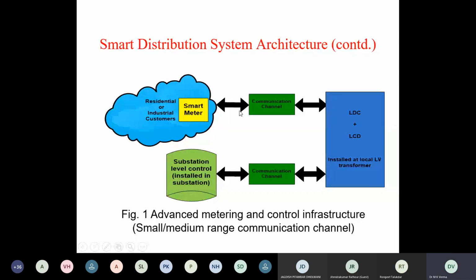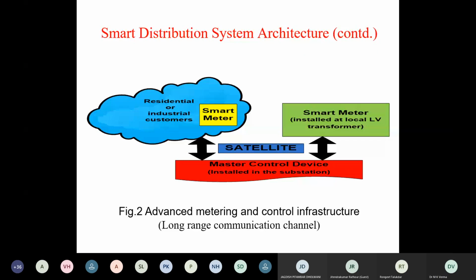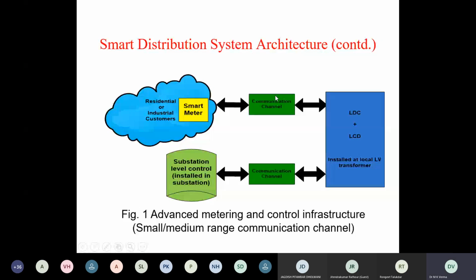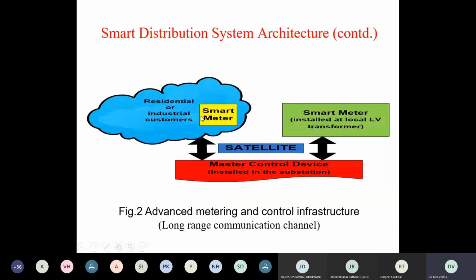The communication may be wired or wireless. For short range communication, it may be wired or wireless, but for long range communication it must be wireless. So it may be through satellite communication. So we have smart meters at residential or industrial consumers, and smart meters installed at the local low voltage distribution transformers, and there is a master controller put at the substation, and these are linked through satellite communication.